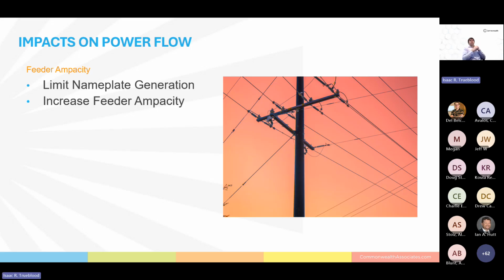Now, if you do want a distributed energy resource and someone is willing to foot the bill for an upgrade, it is the obvious way to mitigate this issue. However, a review of the feeder and potentially any other upstream feeders will be required. I've been on both sides, and often both parties are surprised that a $7 million upgrade is required. It's costly to increase a feeder's ampacity and can often make a distributed energy resource non-economical.